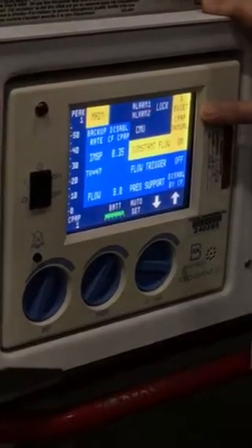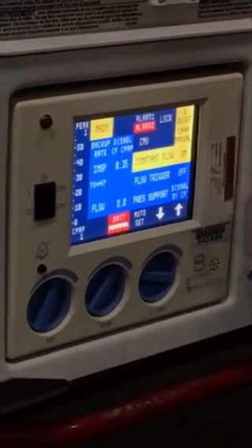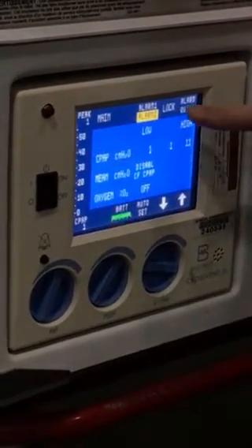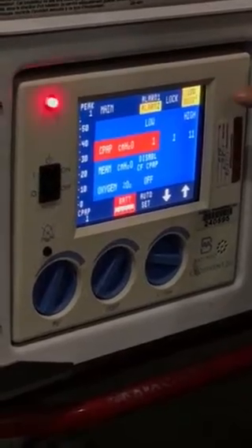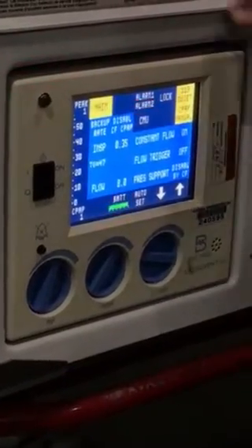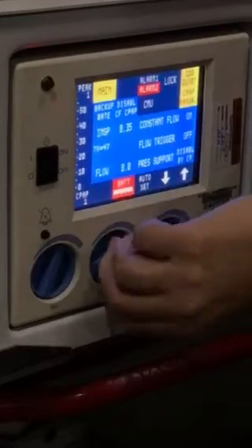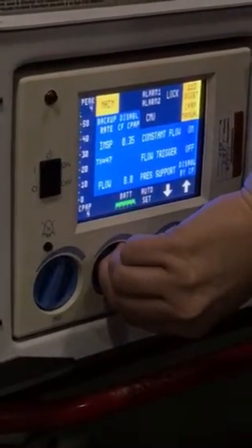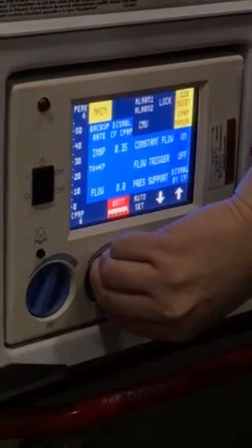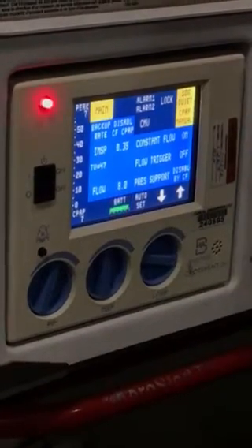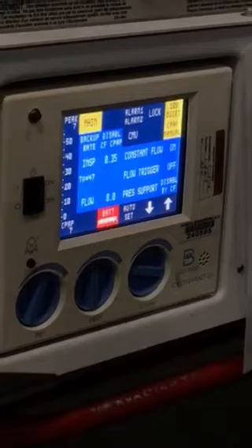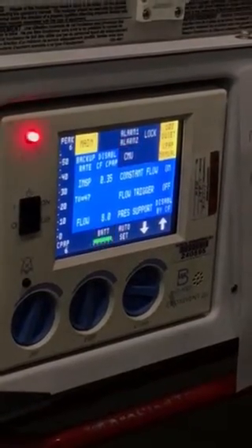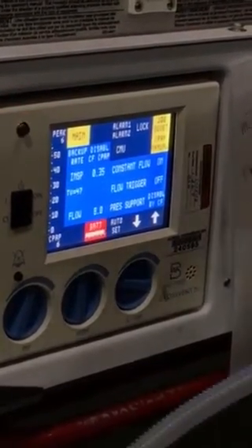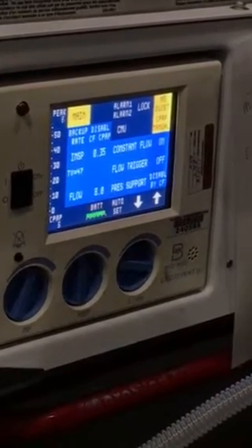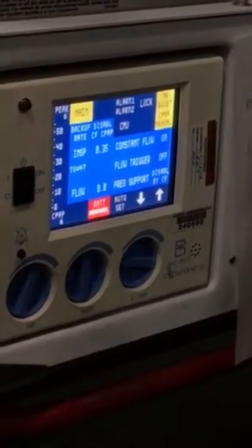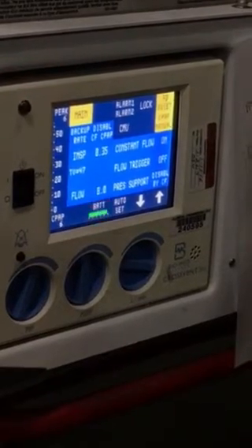So with the CPAP mode, the constant flow goes on, so that takes away the flow trigger, and it takes away the pressure support as well. So then I'm just going to dial in a PEEP. Let's say we're going to do a 7. Okay? And then once you have that dialed in, you just change this to here. You have flow going through here, and then you just blend it. All right? So that's the CPAP.